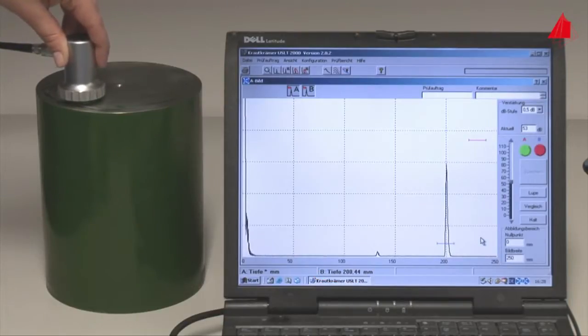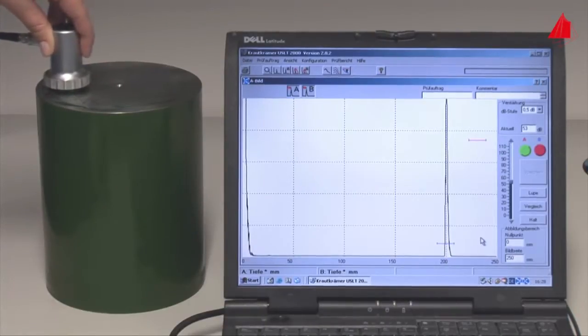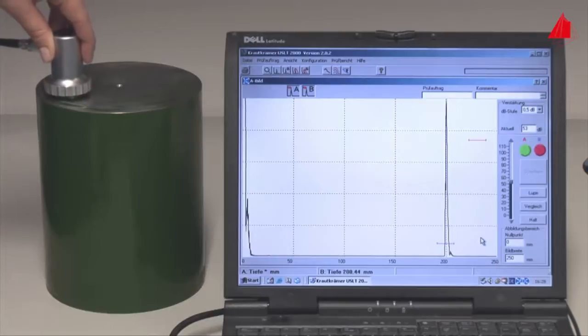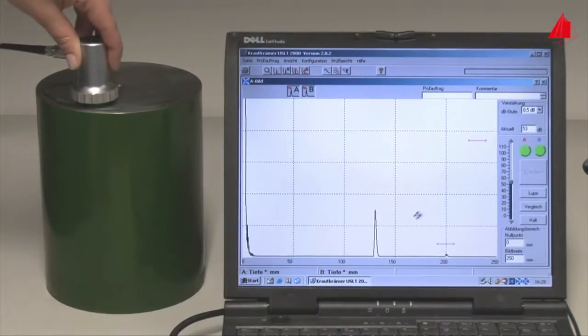And here we go: the material tester scans the upper front end of the cylinder with a probe and observes the monitor. A defect echo appears on the monitor. This defect is located in a depth of 130 millimeters below the surface.